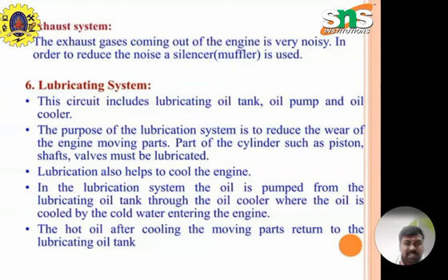The lubricating system. This circuit includes the lubricating oil tank, oil pump and the oil cooler. The purpose of the lubrication system is to reduce the wear of the engine moving parts. Parts of the cylinder such as the piston, shaft and valves must be lubricated. The main function of lubrication is to reduce the wear of the moving parts. Lubrication also helps to cool the engine. In the lubrication system, the oil is pumped from the lubricating oil tank through an oil cooler where the oil is cooled by cold water entering the engine. The hot oil, after cooling the moving parts, returns to the lubricating oil tank.